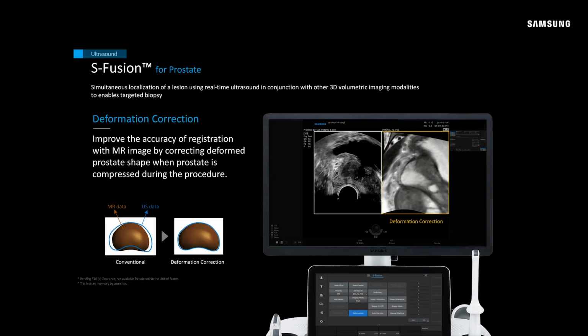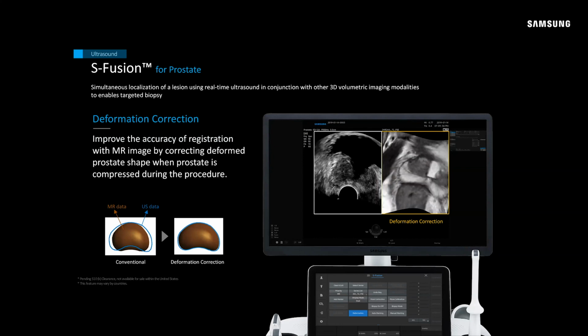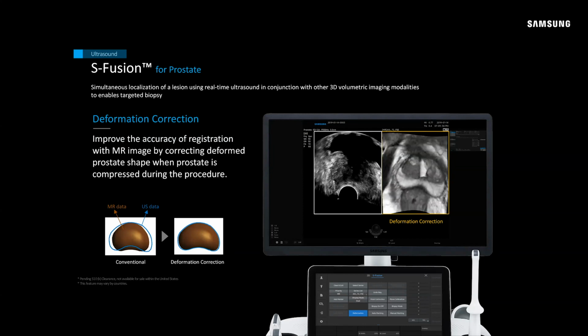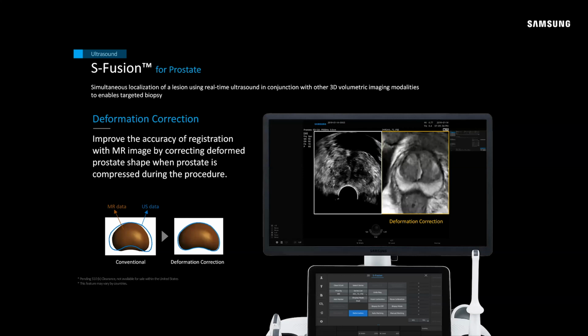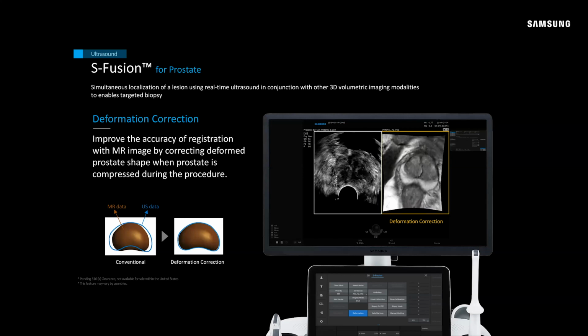The other thing that we know is that when you put a rectal probe in, it deforms the prostate. So the picture that we see on the MRI doesn't always match the picture that we see on the ultrasound, because there's been a change in shape of the prostate. The machine has something called deformation correction. It's actually able to, through AI, reform the prostate on the MRI to match the image that we're seeing on the ultrasound, so that when you target that lesion on the MRI, it's going to correspond to what you see on the ultrasound.